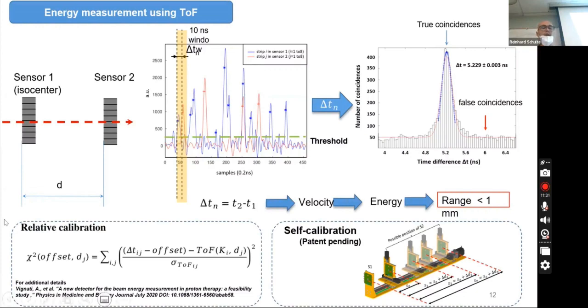So we developed a method we call relative calibration. It is based on chi-square minimization. For more information, you can follow this paper we published. There is a limitation of this method: you need to know beforehand the nominal energy of the facility. So there is a limitation here. For that reason, we moved forward. We created a new method. It's under patent process, with self-calibration, where you don't need to know anything about the facility.